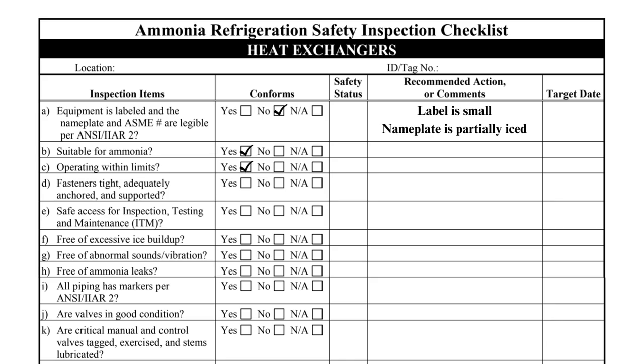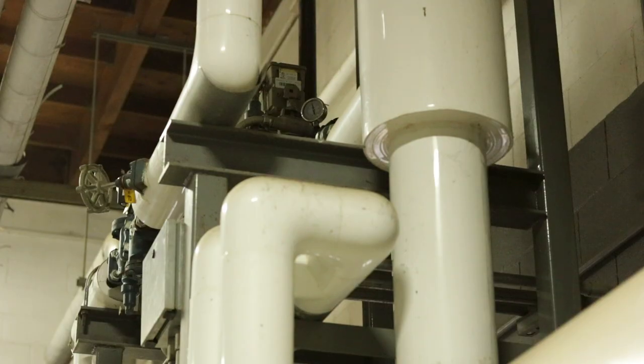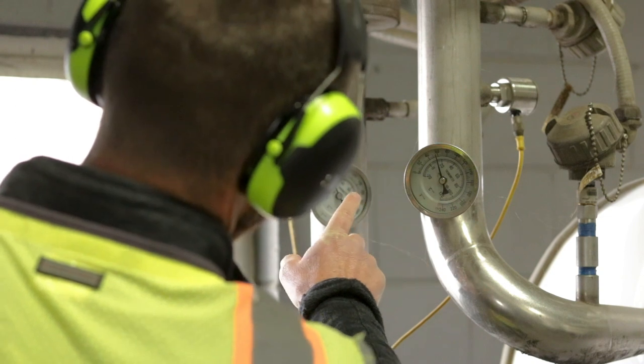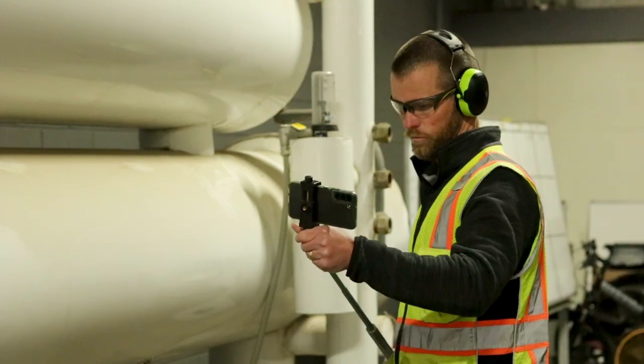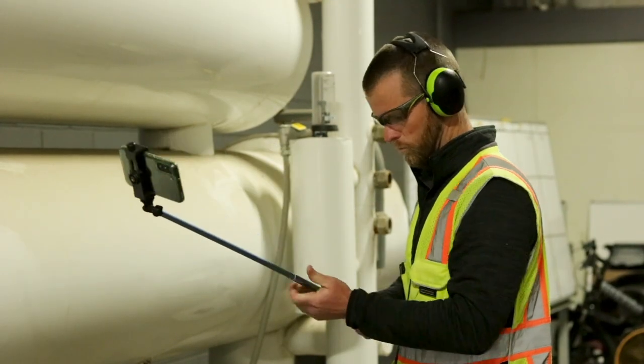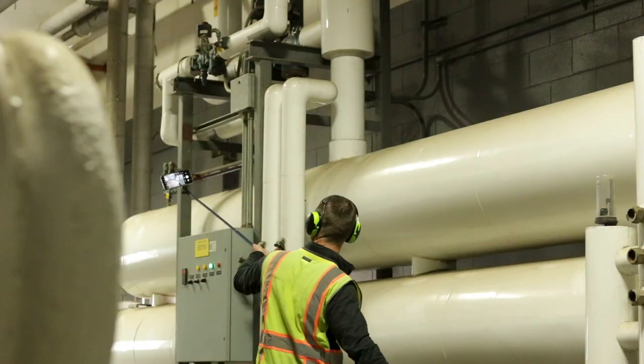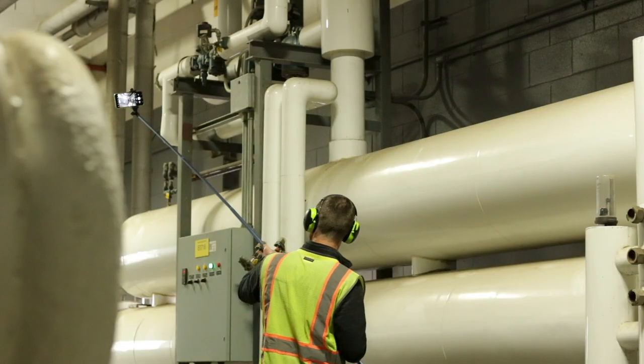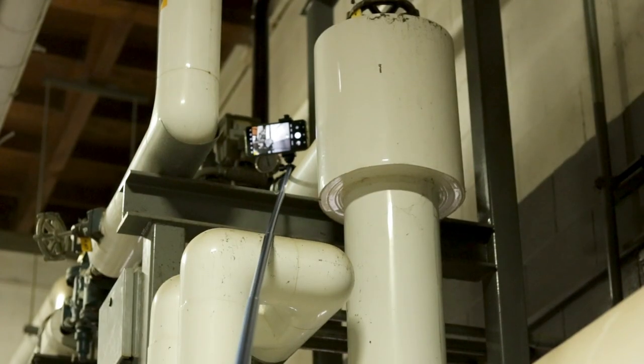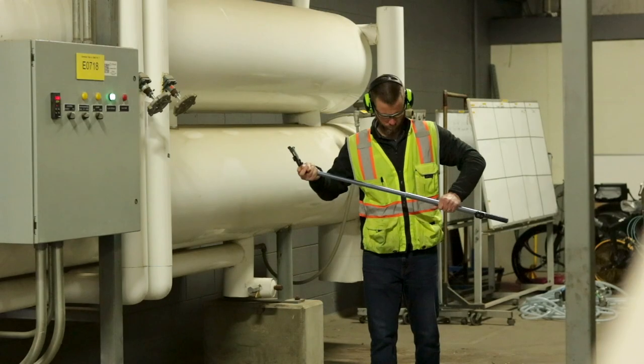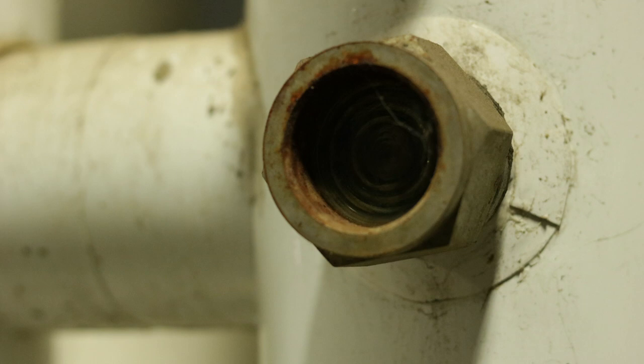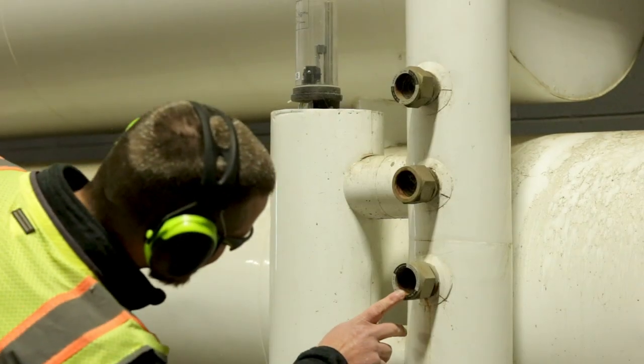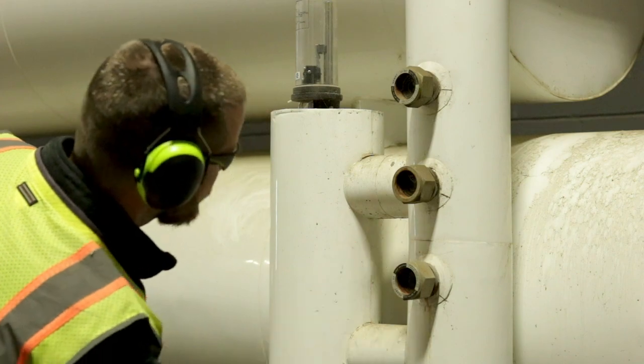Items B and C ask if the heat exchanger is suitable for ammonia and operating within limits. The inspector must verify that the heat exchanger is not constructed of materials such as copper that would degrade if exposed to ammonia. The two primary operating limits of concern are pressure and liquid level. The pressure should be at least 10% lower than the relief valve set pressure. For difficult-to-access gauges, a selfie stick or ladder may be needed to read the gauge. The liquid level in the heat exchanger must have adequate vapor space to accommodate liquid expansion if the heat exchanger experiences an unexpected heat load.